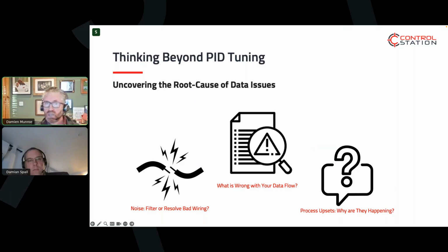Noise and filtering is something you'll see from time to time. Is your instrument starting to fail? Is a component on the instrument board starting to die, causing noise on the system? Probably not - very unlikely - but start by asking: how was this data running last week, last month? When did this change? Oh, it was directly after the shutdown where we had to replace those instruments. Was the shield correctly terminated? Did the instrument technician terminate both ends of the shield rather than only at the panel end? Try to find the root cause of the problem and resolve it there.